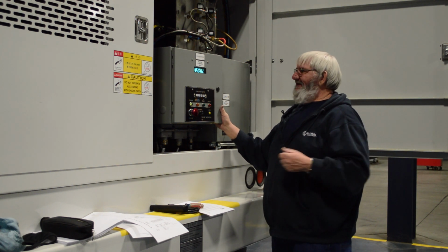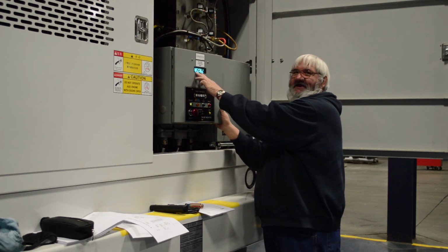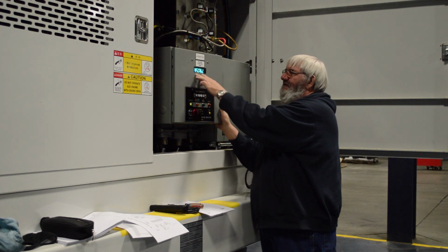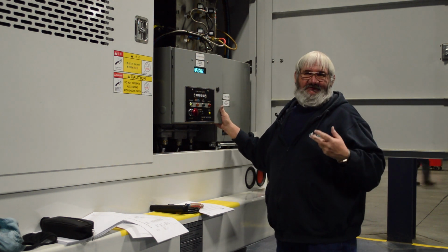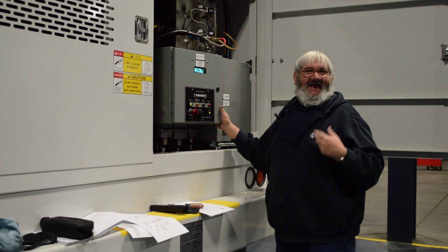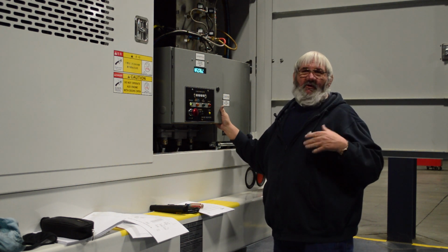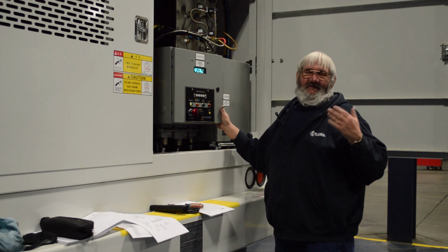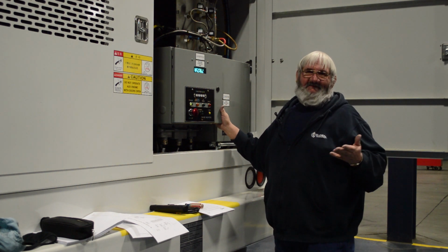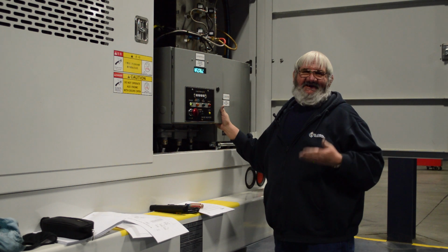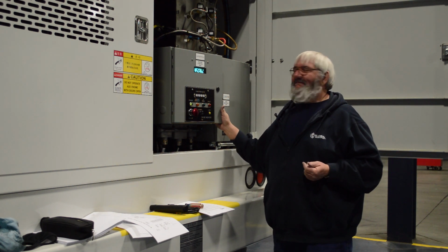Now, here again, make sure you watch your stage final and stage actual. Keep in mind that those two numbers should chase each other and catch each other. If they fail to do that, then the heater will only stage up to the highest stage that it can maintain temperature at.